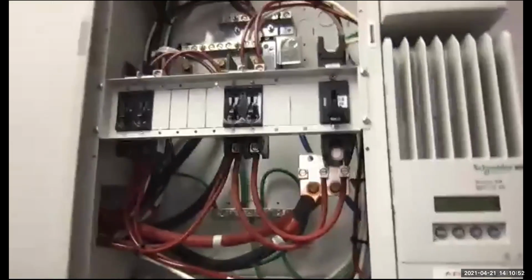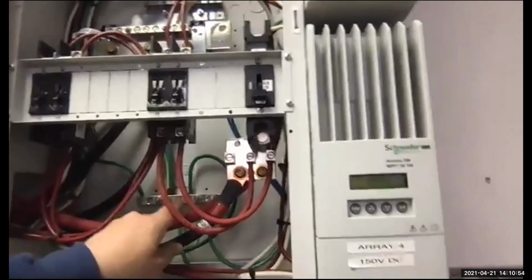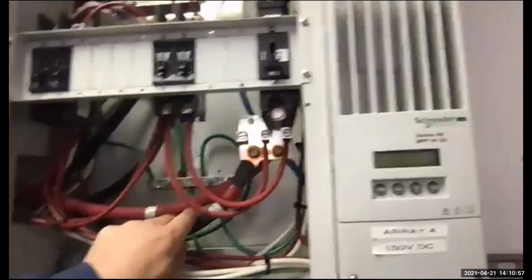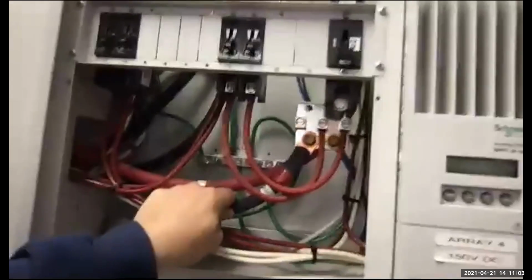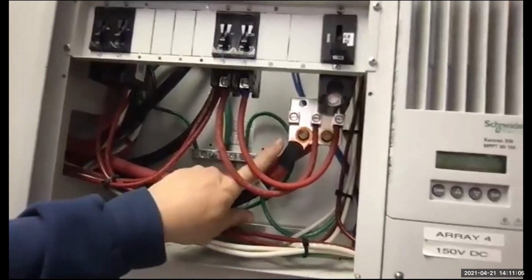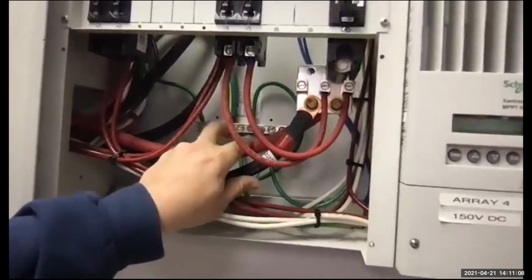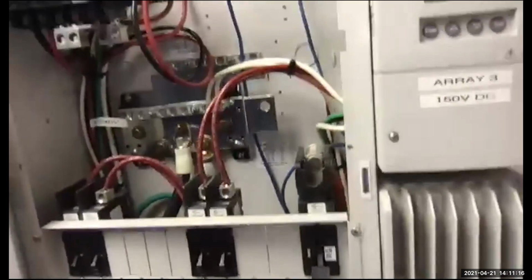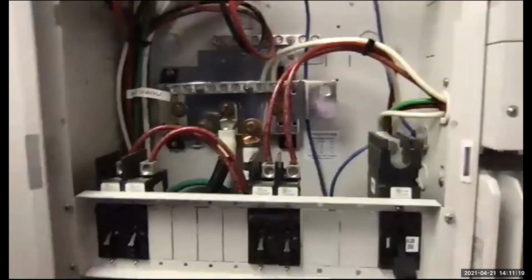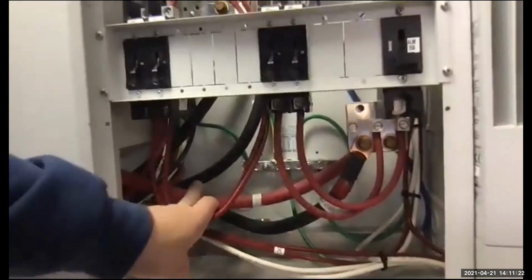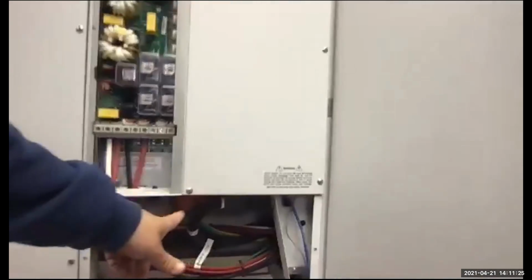So the batteries come to this bar here or here. I have to figure out which cable it is. Looks to me like, yeah, this is the cable coming from the battery. So this cable goes to the battery, goes to this bus bar, and then we actually have this cable here that is on the top side of this breaker. The top side of this breaker, then this big fat red cable runs all the way over here to our inverter. So just to be clear, we have our batteries over here.